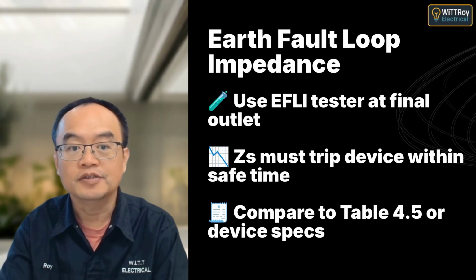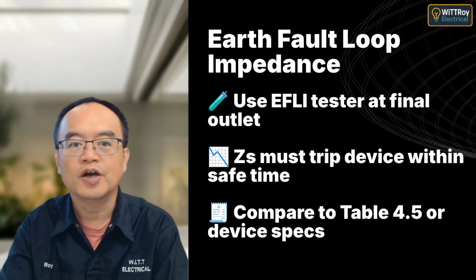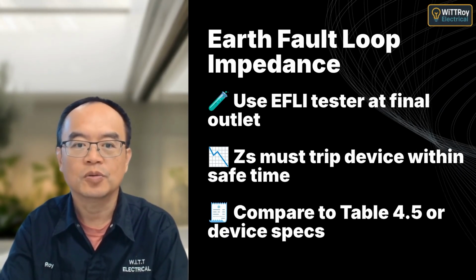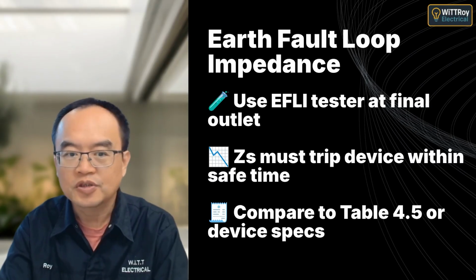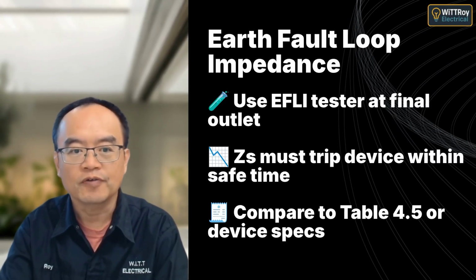Measure loop impedance at the furthest outlet. The Zs value must allow the protective device to operate quickly in a fault. Use device curves or table 4.5 to verify compliance.